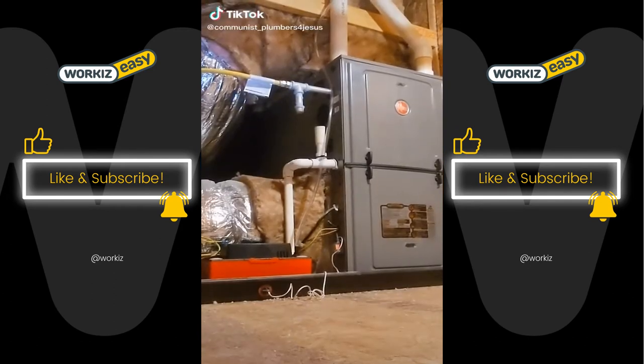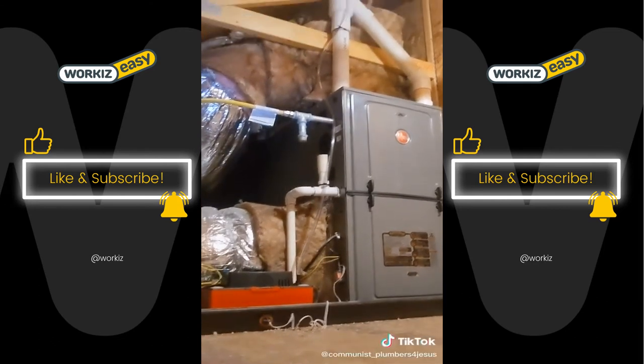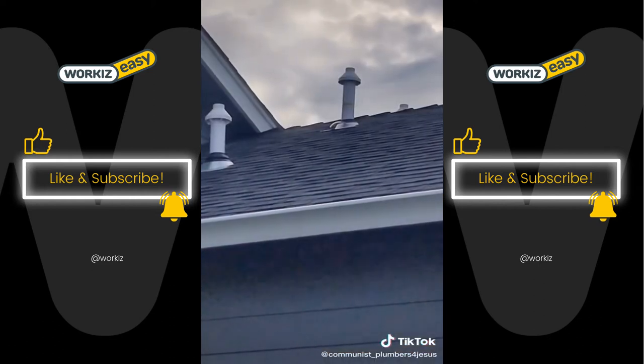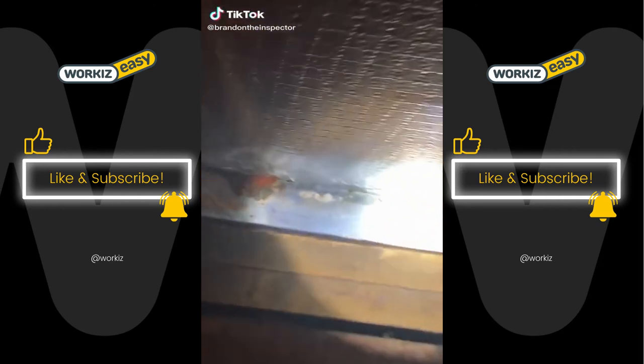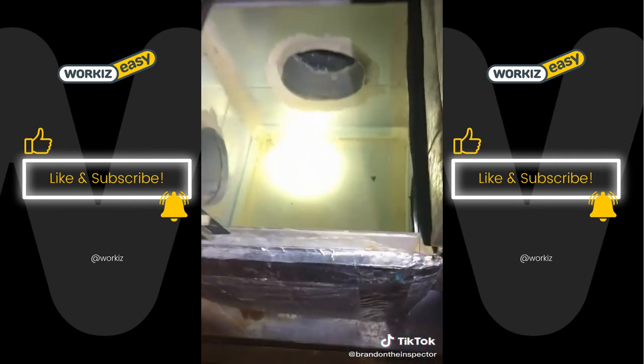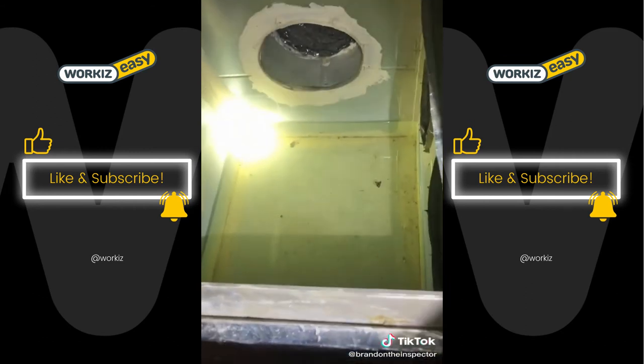Probably. So anyone ever seen this before? Sending acidic condensate out a vent? Just look at that. Right out the side. Clue number one, something is wrong. We have moisture at the bottom of our return in the drain pan. Insulation is wet to the touch. And then upon taking off the cover to the air handler, it's about 2 inches of staining water inside of our return. I'd say we need some work.